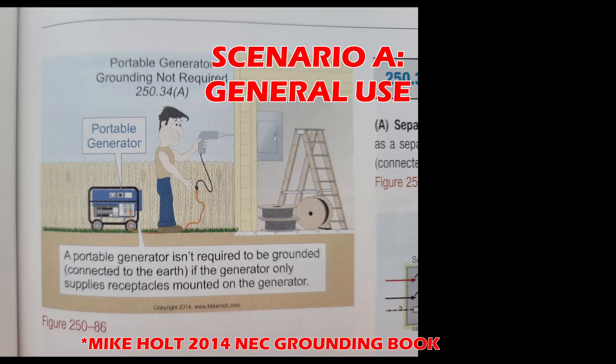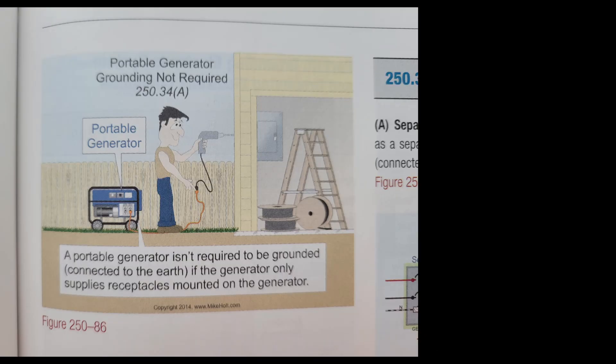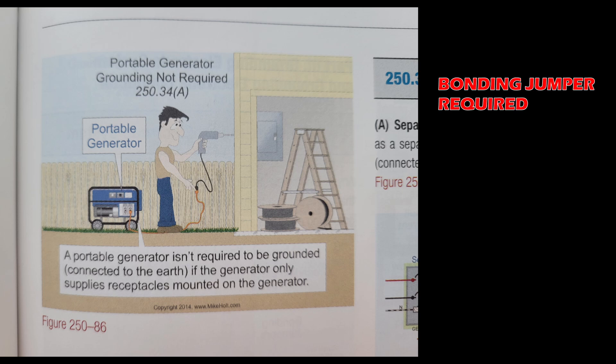In this scenario, you are using your generator at a construction site or similar, where you have appliances or tools plugged in directly to the 20 amp GFCI receptacles. In this case, the neutral to ground bonding jumper is required to stay in place and you do not need to install a ground rod.